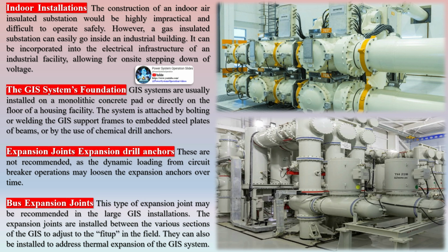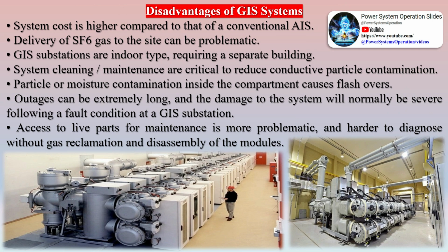Bus expansion joints may be recommended in large GIS installations. The expansion joints are installed between the various sections of the GIS to adjust to the fit-up in the field. They can also be installed to address thermal expansion of the GIS system.